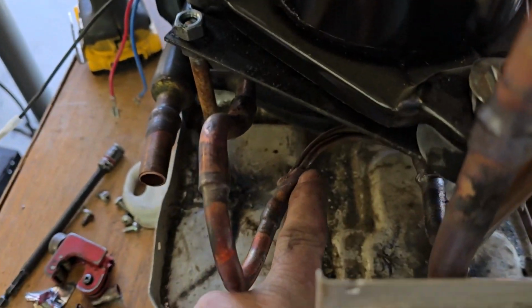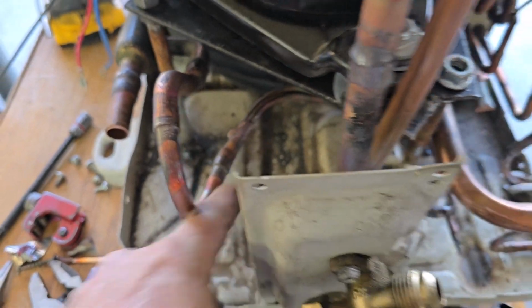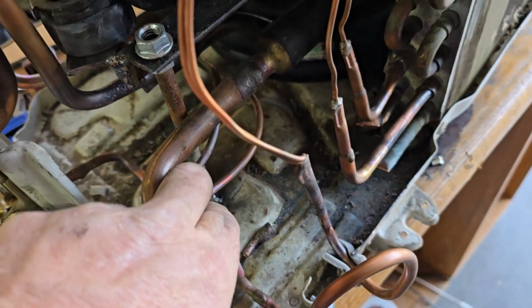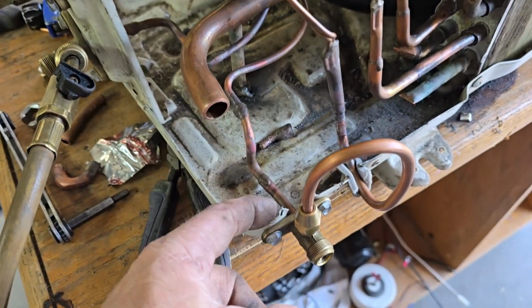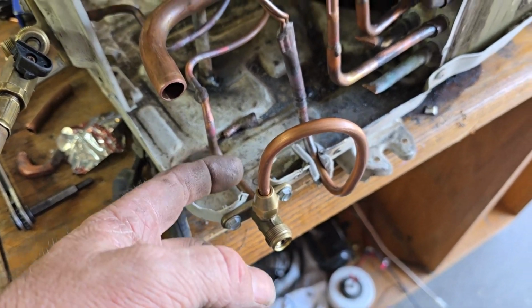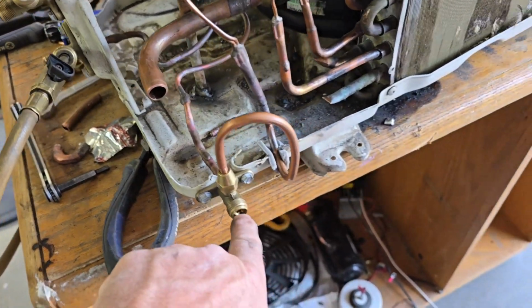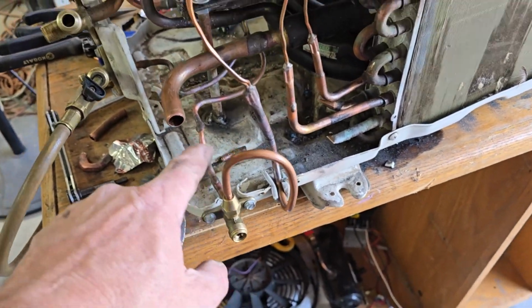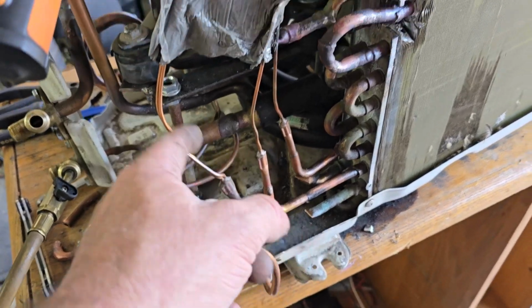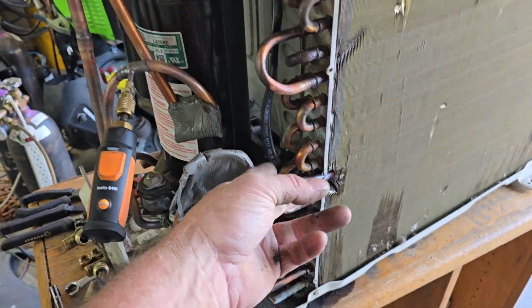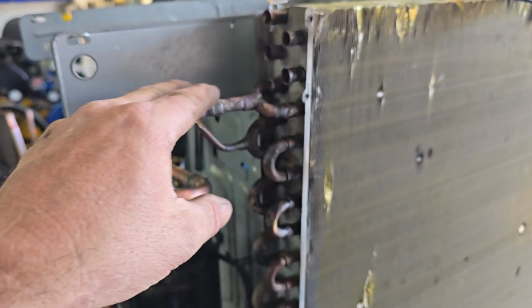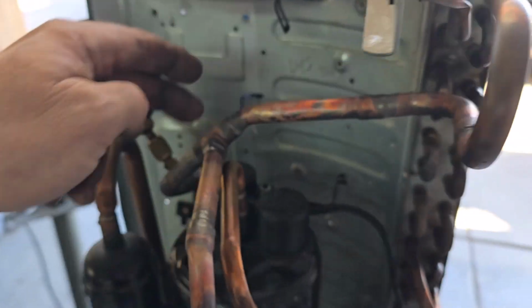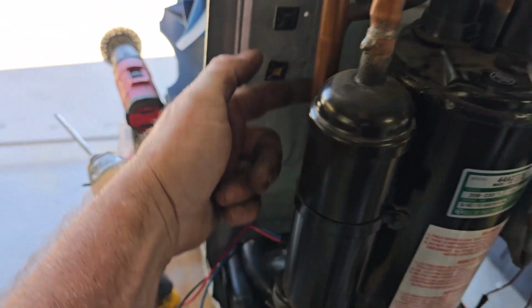This is just a part I took off something else, so it's already a good splitter. I split the liquid line, one going this way for this coil. If I open this one, it's going to go through here, hit the capillary tube, feed the two circuits I made, go up, crisscross, go up, come out, suction, hit this T, draw down into the compressor.